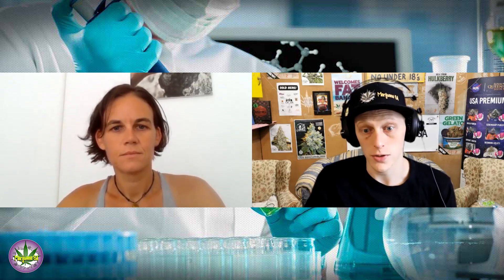It's quite an important thing to notice — when getting tests done you've got to make sure it's at a facility using a calibrated machine. The lab should be doing this, calibrating regularly. It's a process to import the reference samples and calibrate off them, but that's just part of the maintenance.